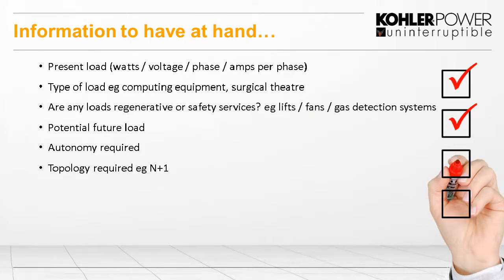So what do you need to do and what do you need to know when you're planning a UPS installation? Obviously, we need to know what the present load is, in watts, kilowatts, or amps. What type of load is it? Is it computer equipment? Is it surgical equipment? That type of information is very important because it can be regenerative or a safety service, and that will require certain design criteria that we need to know as well.